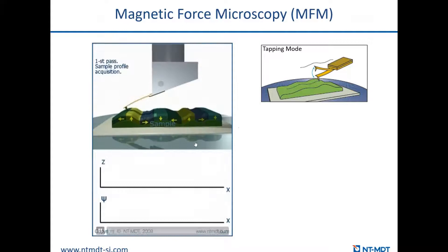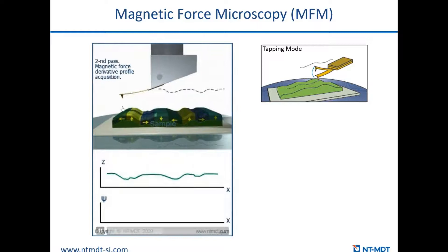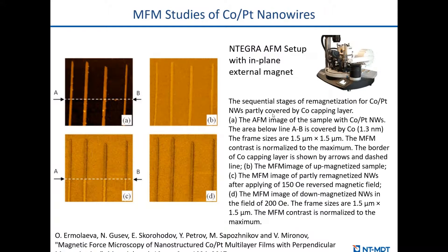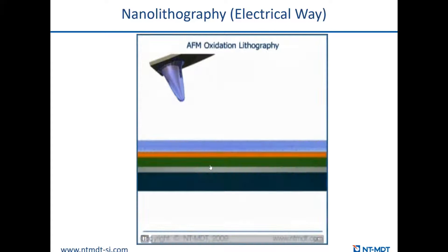A few words about magnetic force microscopy. If we use a magnetized tip, we can measure the magnetic response of the sample if it has magnetization in different directions. We can also apply an external magnetic field — controlled from the software — in both vertical and in-plane directions. For example, you can see how the domain structure of yttrium iron garnet changes with applying different values of magnetic field in the vertical direction. Our customers also applied the magnetic field in-plane, looking at how the magnetic polarization of nanowires is changing.